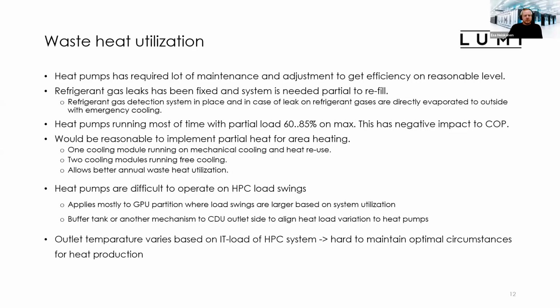Then about the waste heat utilization, this heat pump has required a lot of maintenance and adjustment to get efficiency to a reasonable level. Well, one reason for that is that this integrated system test, which we did in spring of 21, was made with 2 megawatt heat load with those heat pumps, and adjustments were done, but there was a long delay before we again had that high power usage in the Lumi directly cooled partition.